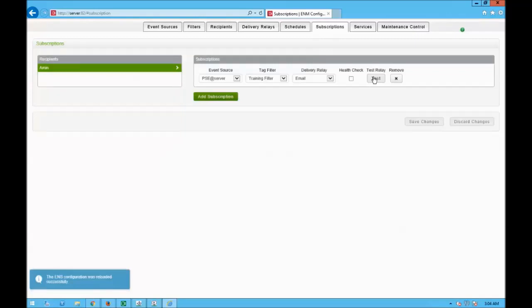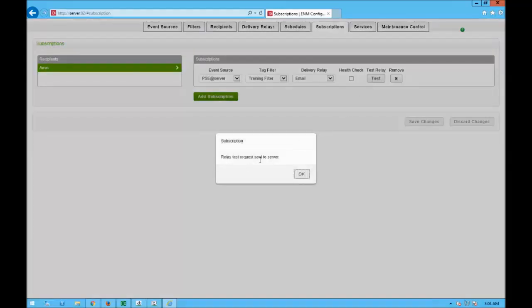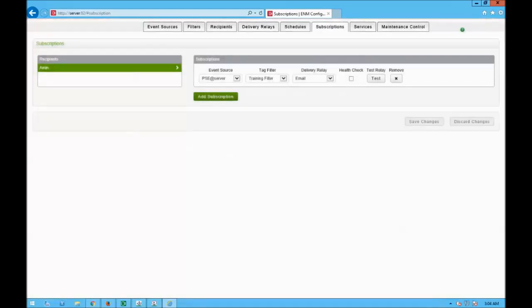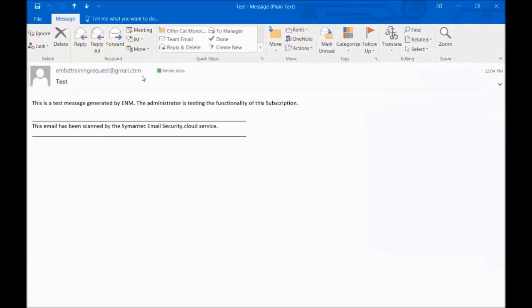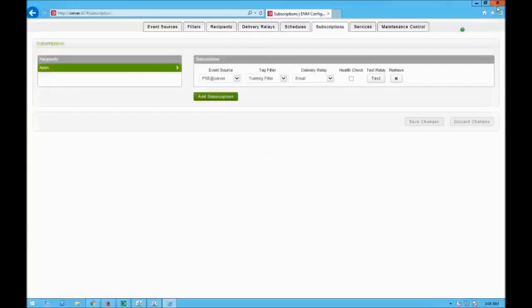I don't want to wait until I have an alarm and then realize I'm not receiving anything because my configuration is wrong. So I click on test relay — a test request is sent to the server. I click OK, check my inbox, and I can see a message from my ENM training account: 'This is a test message generated by ENM — the administrator is testing the functionality of this subscription.' Now I'm sure my relay is functioning.